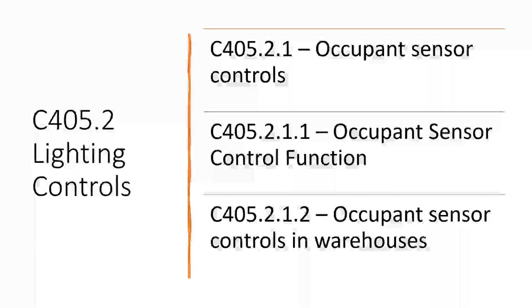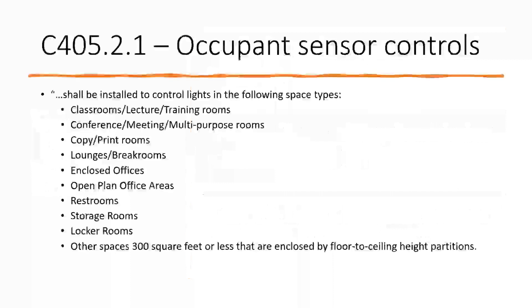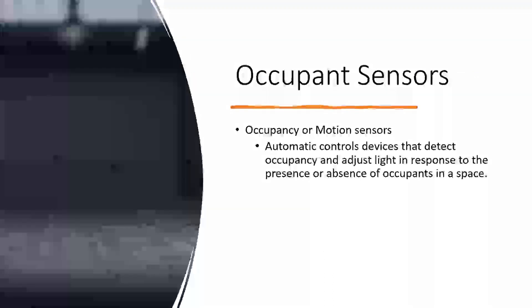Occupancy sensor controls are broken down into three sections: what is an occupancy sensor, the control functions, and special cases for warehouses and open office layouts. They shall be installed to control lights in the following space types — it's pretty straightforward and correlates with the space-by-space method. The main caveat is that 'other spaces' of 300 square feet or less that are enclosed by floor-to-ceiling height partitions are included — this is meant to encompass all the random rooms like mechanical, electrical, janitorial, storage, and laundry spaces.